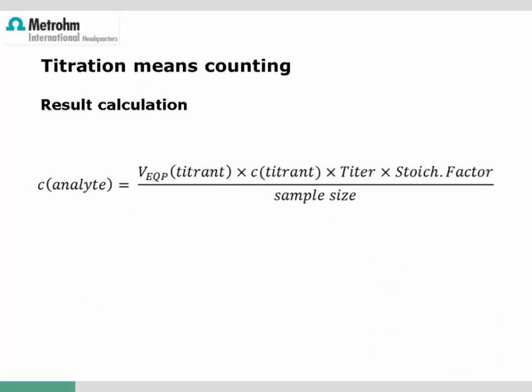When all required variables are available, we can calculate the result. The concentration of the analyte is the product of the volume at the equivalence point times the titrant concentration times the titer value and the stoichiometric factor, all divided by the sample size. The advantage of modern titration instruments is that the calculation of the final result is done directly after the titration is finished. However, the best calculation formula is useless if the indication of the end or equivalence point is not correct.